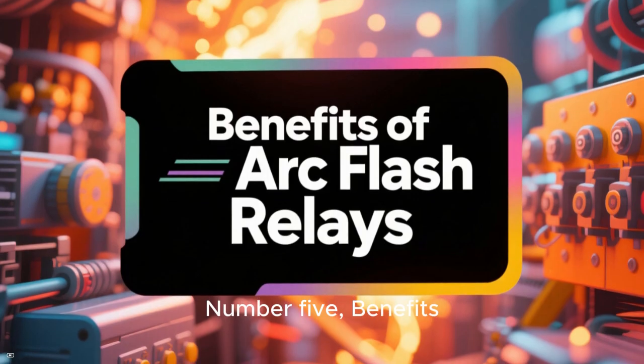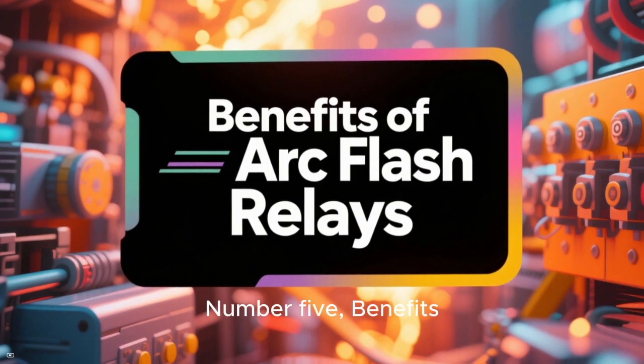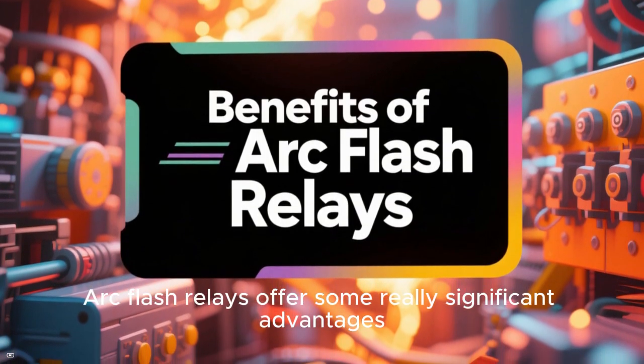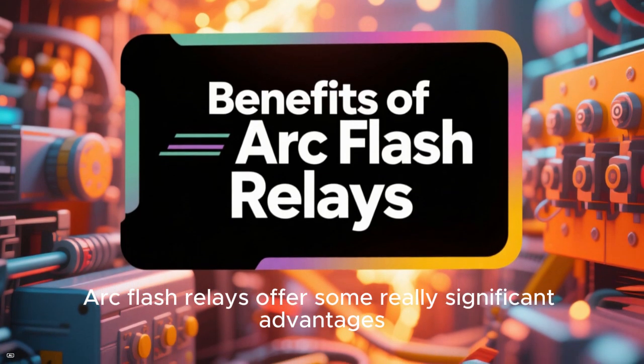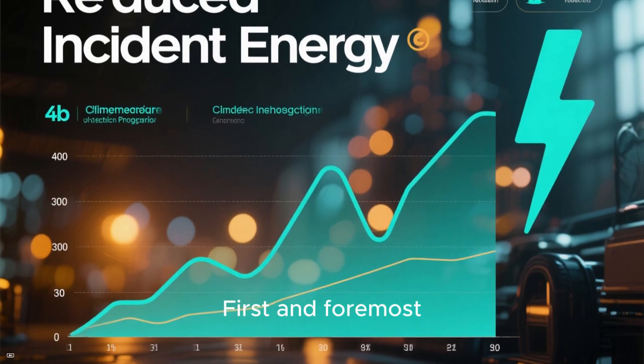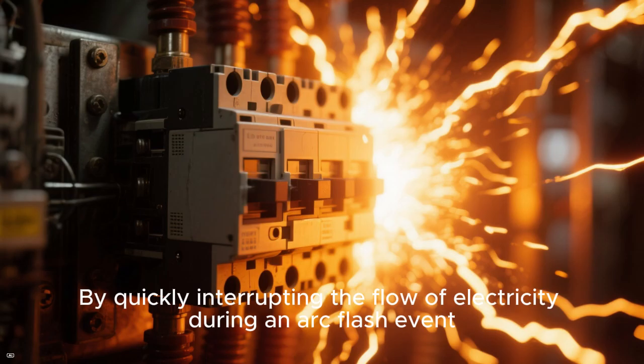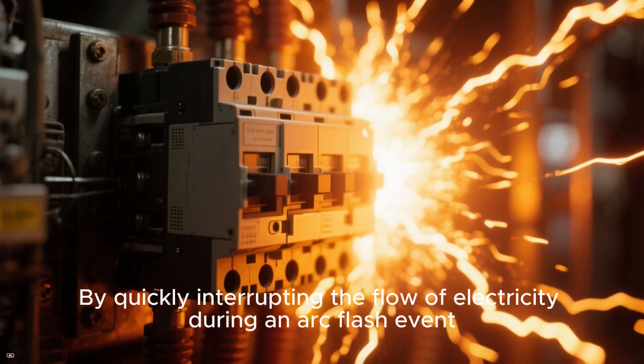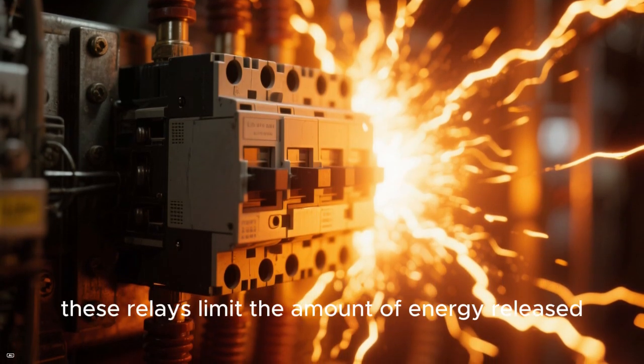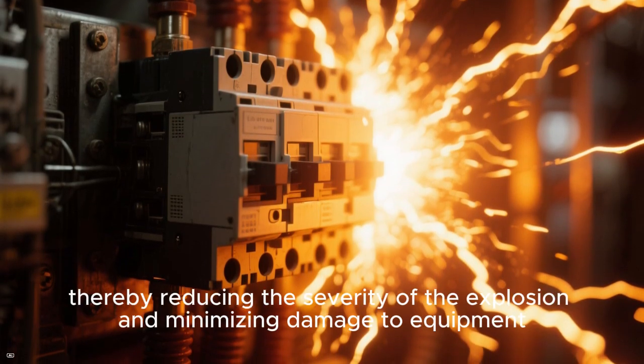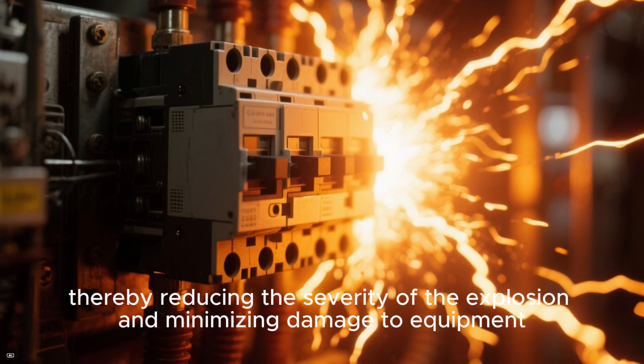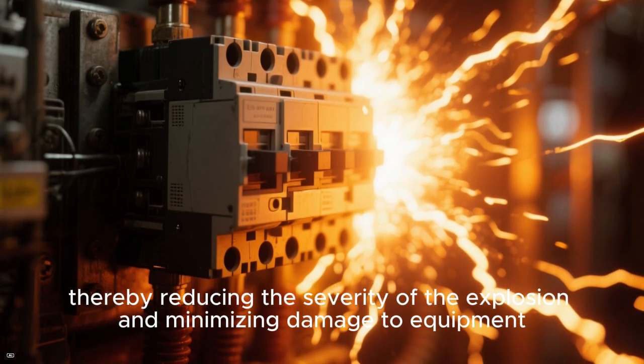Now, let's talk benefits. Number 5, benefits. Arc flash relays offer some really significant advantages. First and foremost, they reduce the incident energy. By quickly interrupting the flow of electricity during an arc flash event, these relays limit the amount of energy released, thereby reducing the severity of the explosion and minimizing damage to equipment.